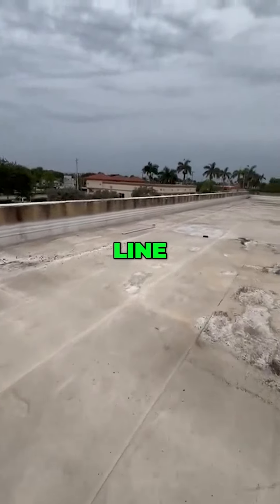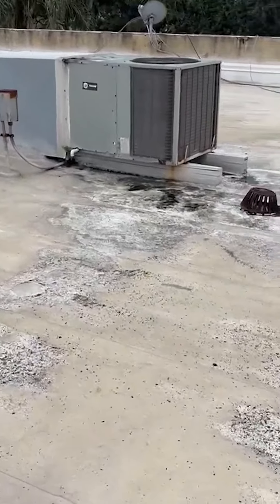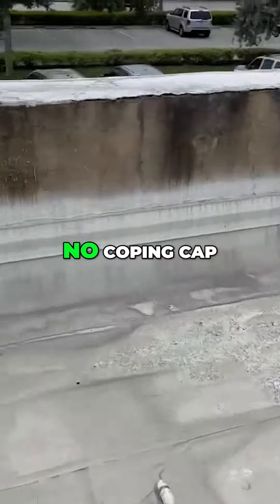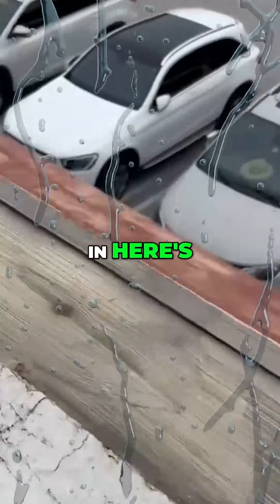There's little things here. There's another drain line. This roof hasn't been maintained in a while — stuff blowing around, so that pipe should be over here. You're dripping off of the air conditioner there, drain cages not properly installed, gunk everywhere, no coping cap right here. So you've got water coming in.